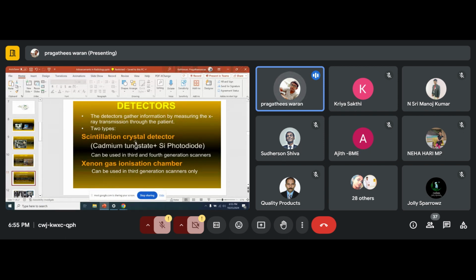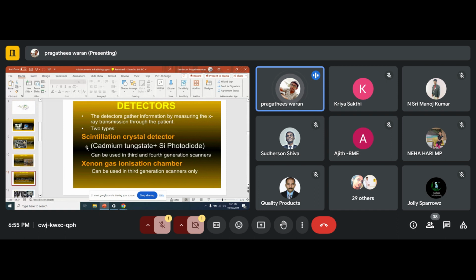What the scintillation detector does is, once the X-rays are produced and fall on the detectors, the scintillator produces minute light signals. Below the scintillation detectors, photodiodes will be there. The photodiodes capture the light signals and measure them. Then it processes them and produces an image. That is what the scintillation crystal detectors do.